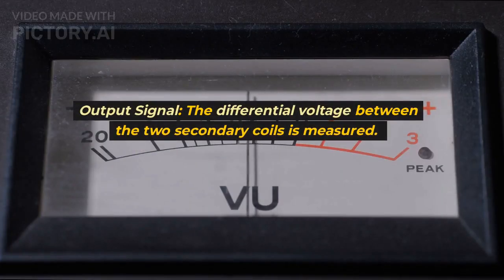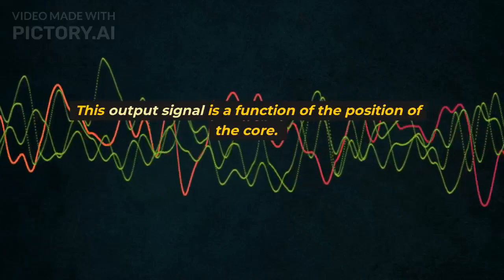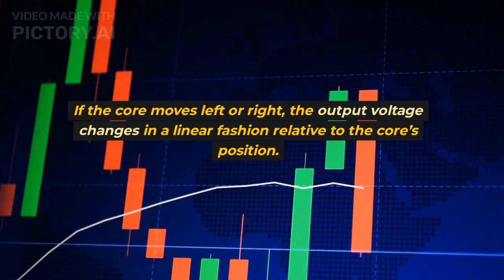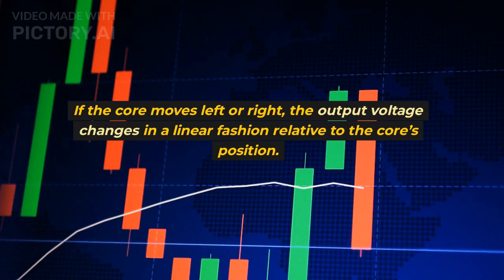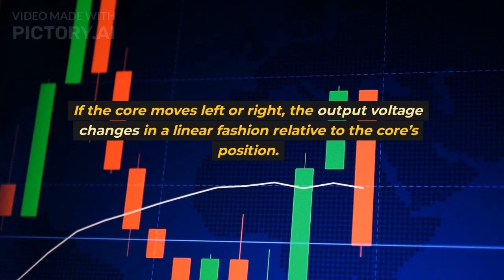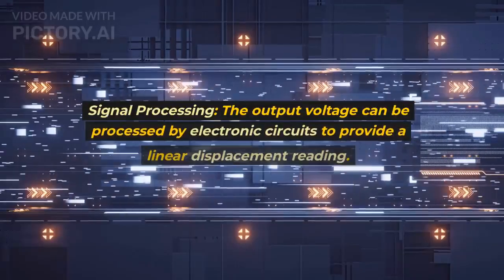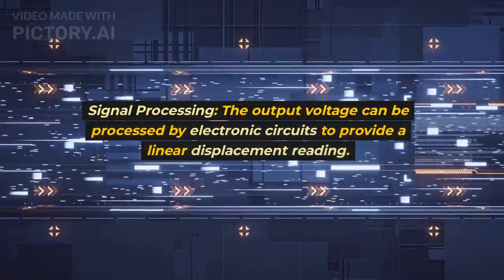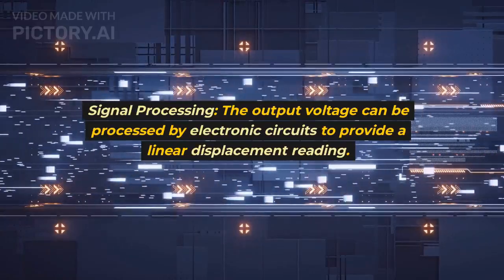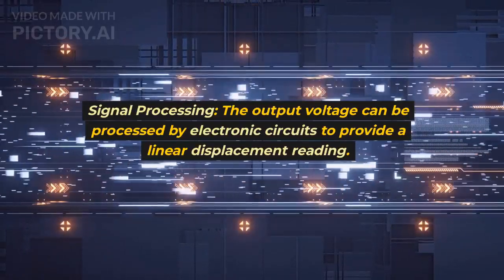Output signal. The differential voltage between the two secondary coils is measured. This output signal is a function of the position of the core. If the core moves left or right, the output voltage changes in a linear fashion relative to the core's position. Signal processing. The output voltage can be processed by electronic circuits to provide a linear displacement reading.